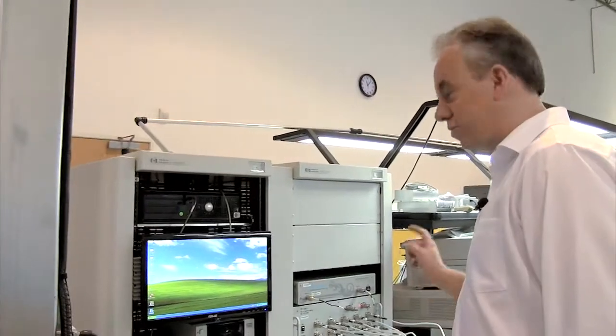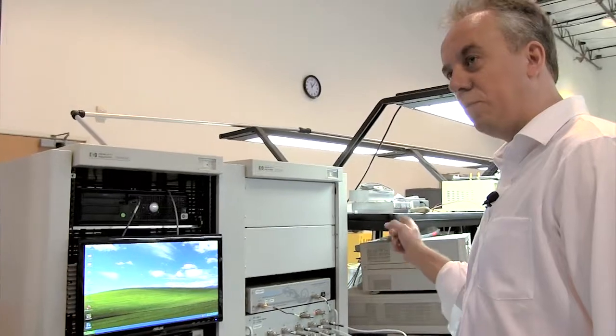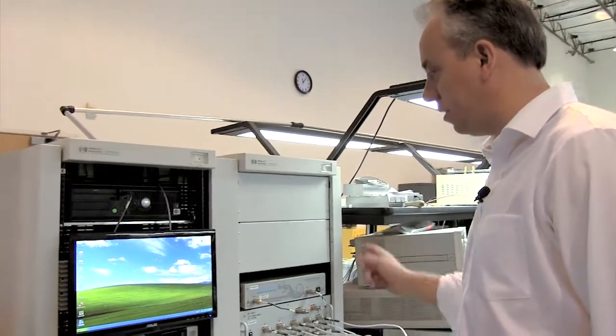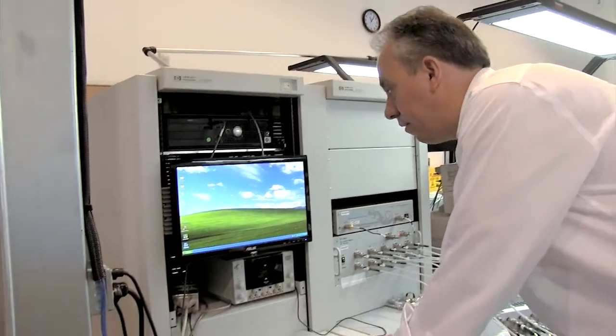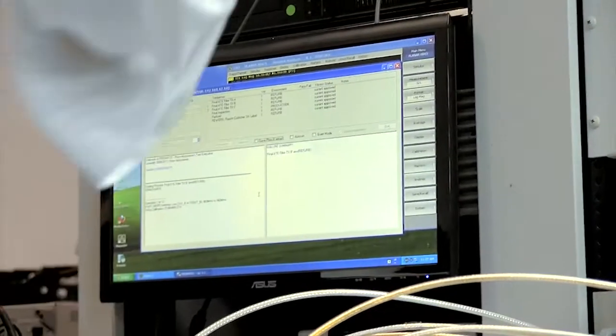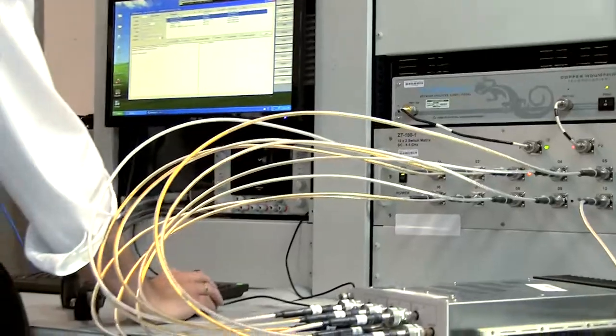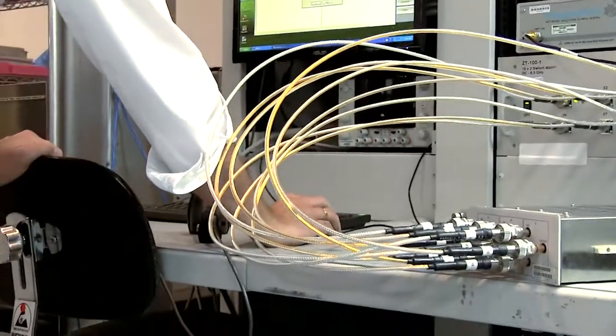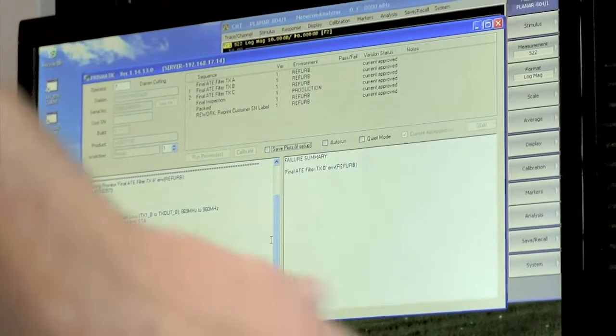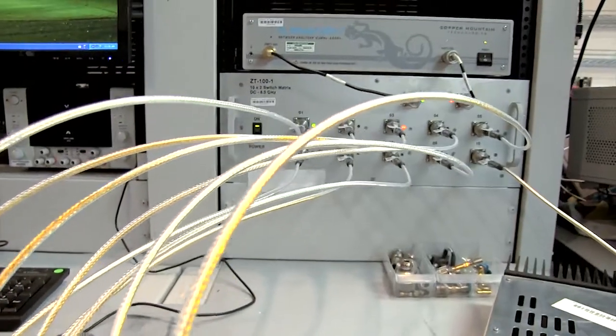So the great thing about the Copper Mountain analyzer is its versatility. We've just managed to bring it over and stick it in our production test machine here. We can fire up our internal test software and our software can automatically control the Copper Mountain analyzer and the switch matrix to create a multi-port test system here and switch through and test our product.